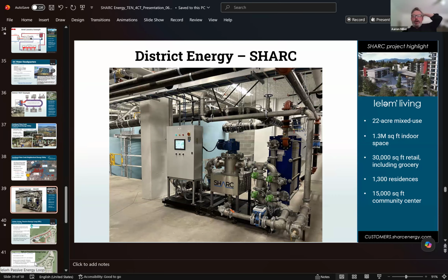Well, that's a great question. Those YTK heat pumps, they're massive. Imagine a ginormous natural gas boiler for a huge commercial building. We're talking that size. So that's more of a municipal district level heat pump. You're spot on, this is not just a problem for us. It's electrification in general, building modernization in general. It's hard because a lot of these buildings, I'm just north of Manhattan, are Con Ed steam buildings or buildings built for internal steam. To convert them over to hydronics is a fool's errand because it'll never pencil.